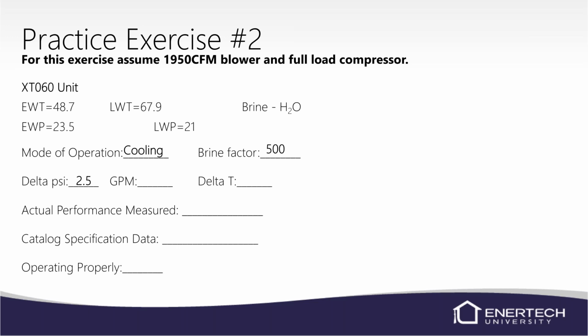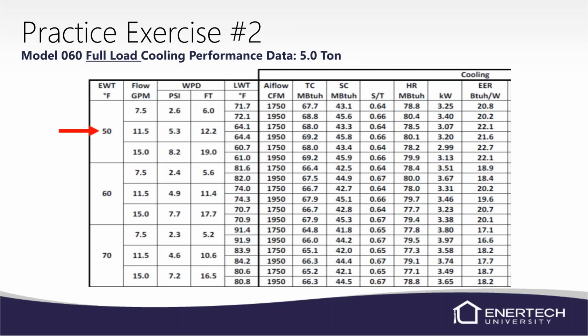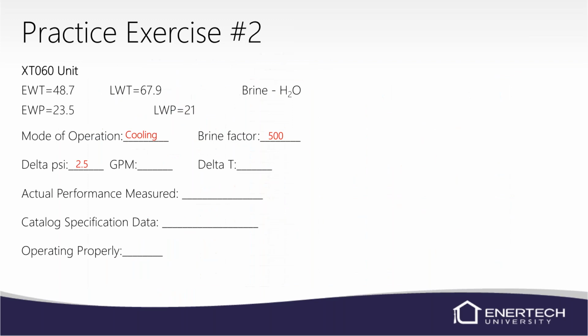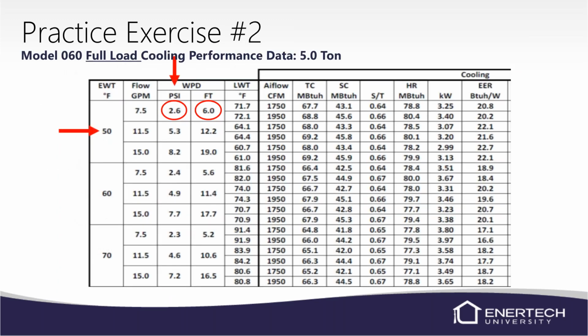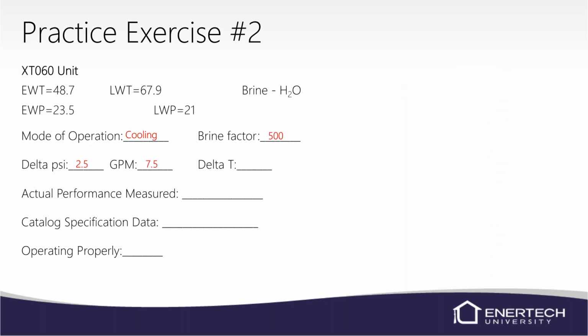We know our pressure drop of 2.5, but we don't know our GPM. So we know our entering water temperature is roughly 50 degrees, and we know our pressure drop. So we'll go back to the manual. We've got 50 degree entering water temperature, a 2.5 pound pressure drop. Sorry, I need to move that circle over. Sorry about that. Because we're not looking at feet of head, we're looking at PSI. So that 2.5 pressure drop is equal to 7.5 GPM, right next to it. Flow in GPM, 7.5. So we know our GPM.